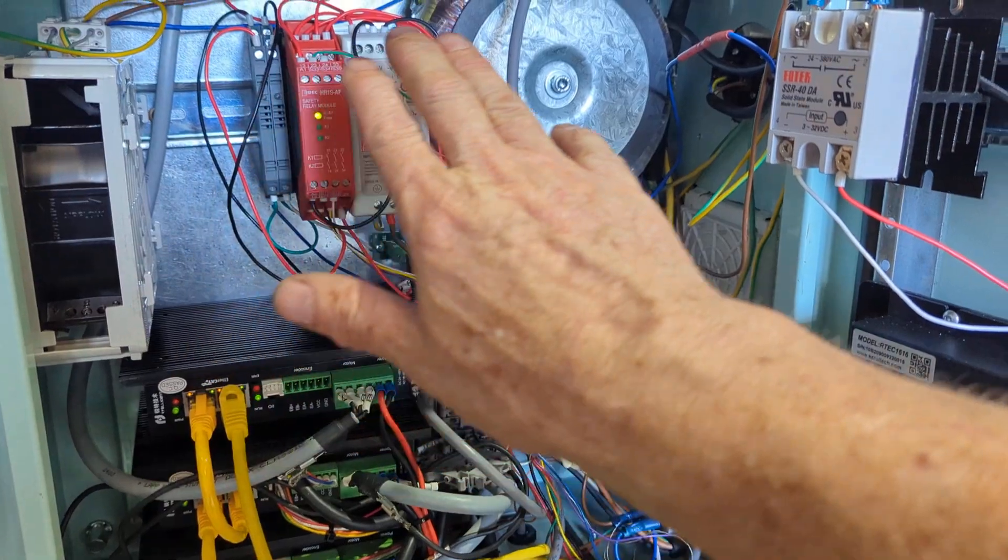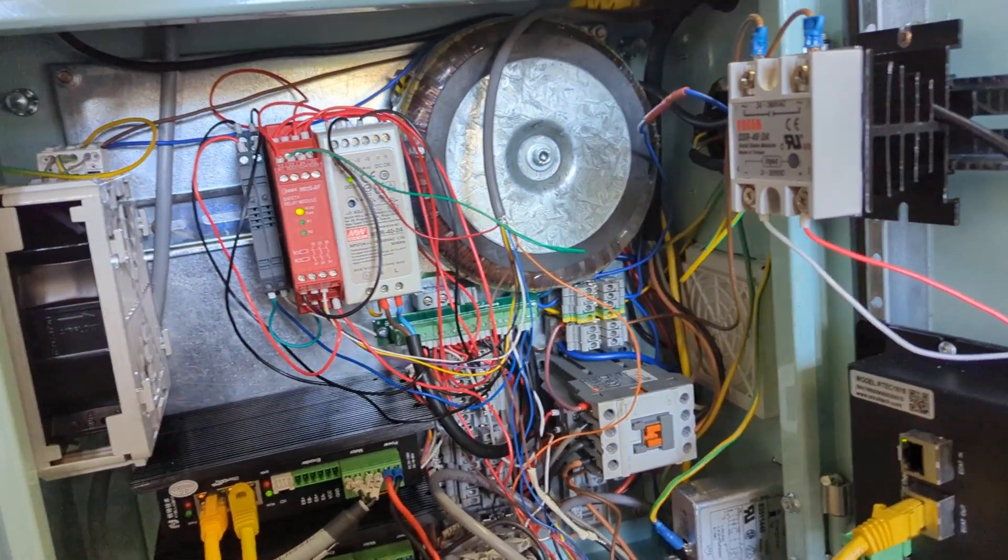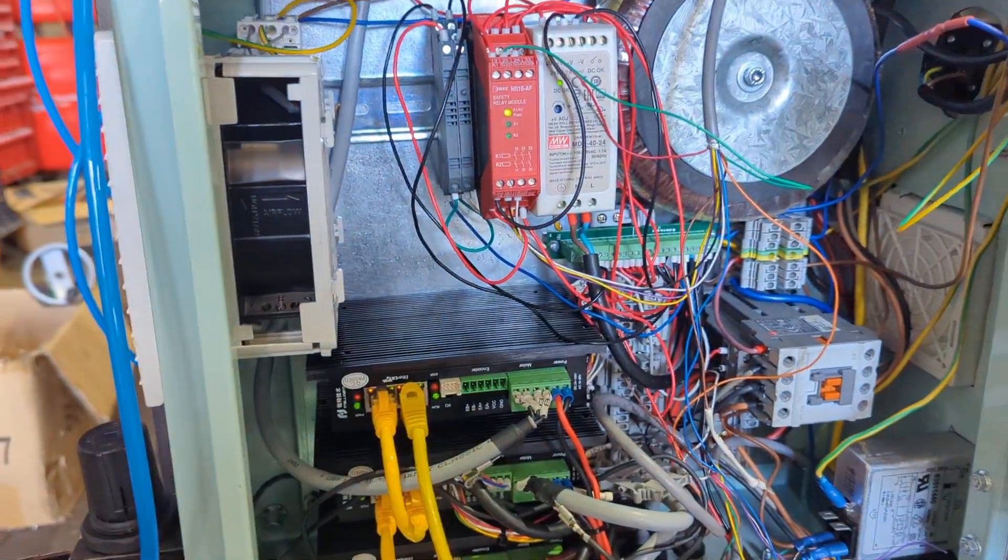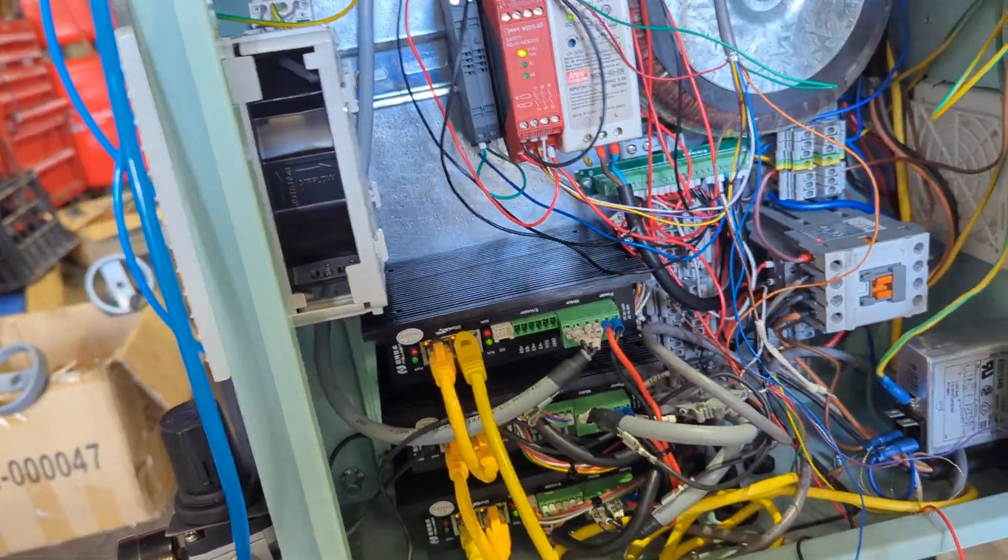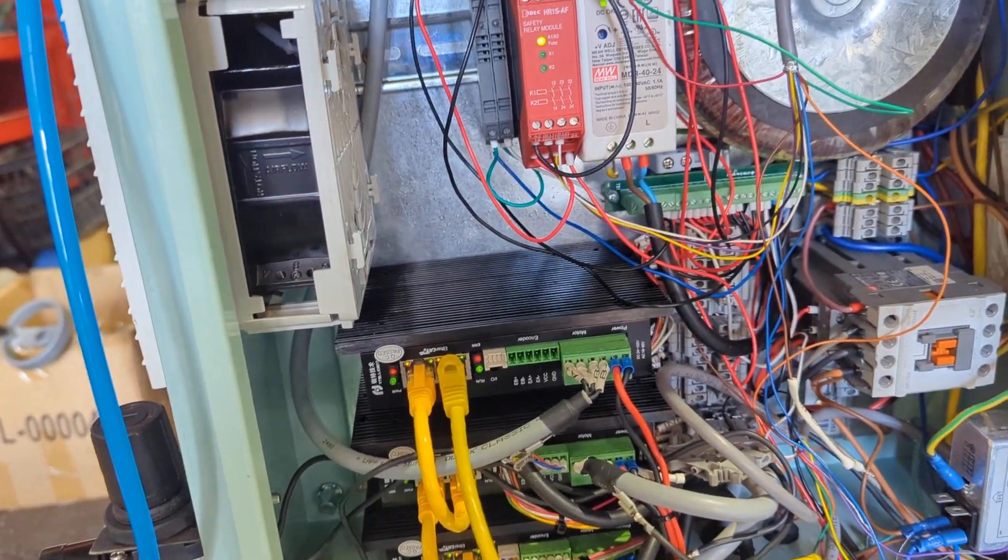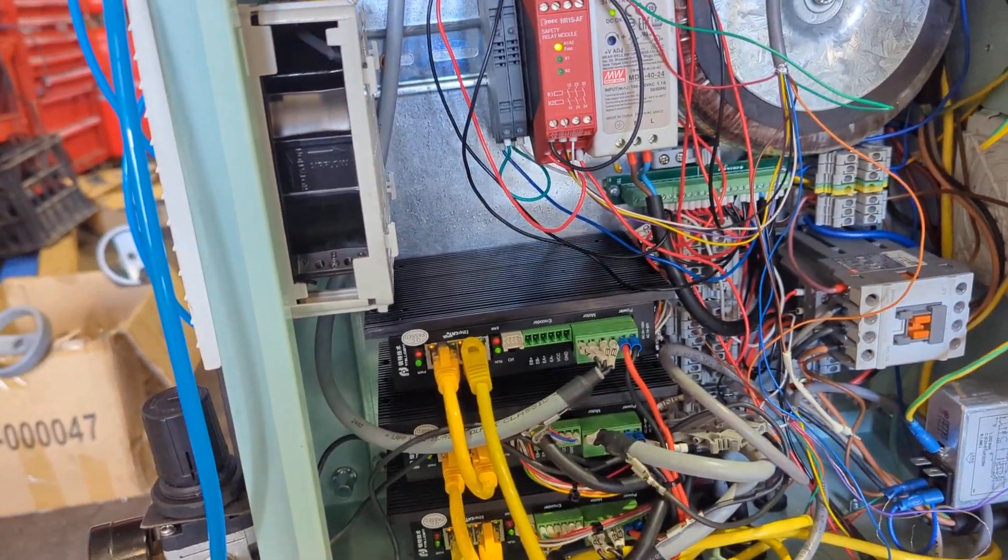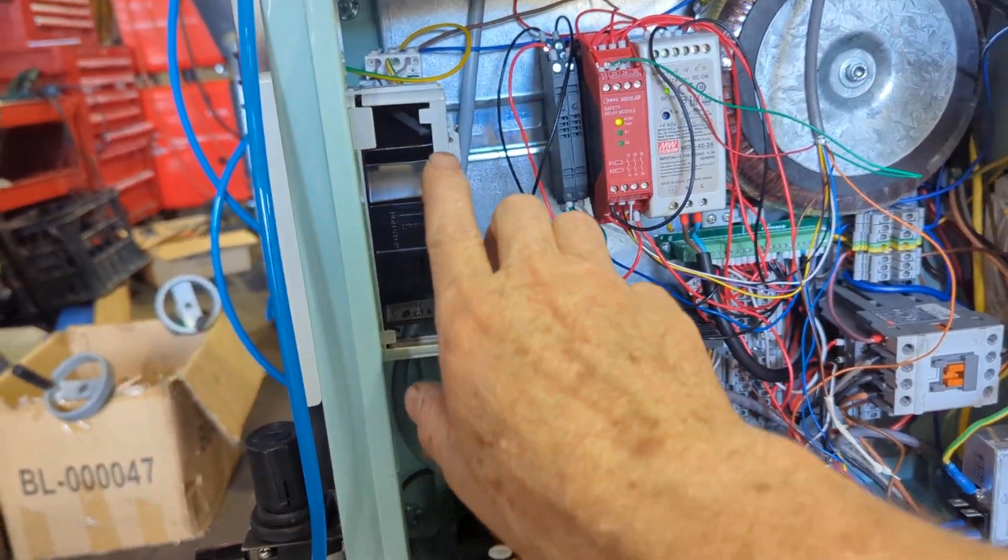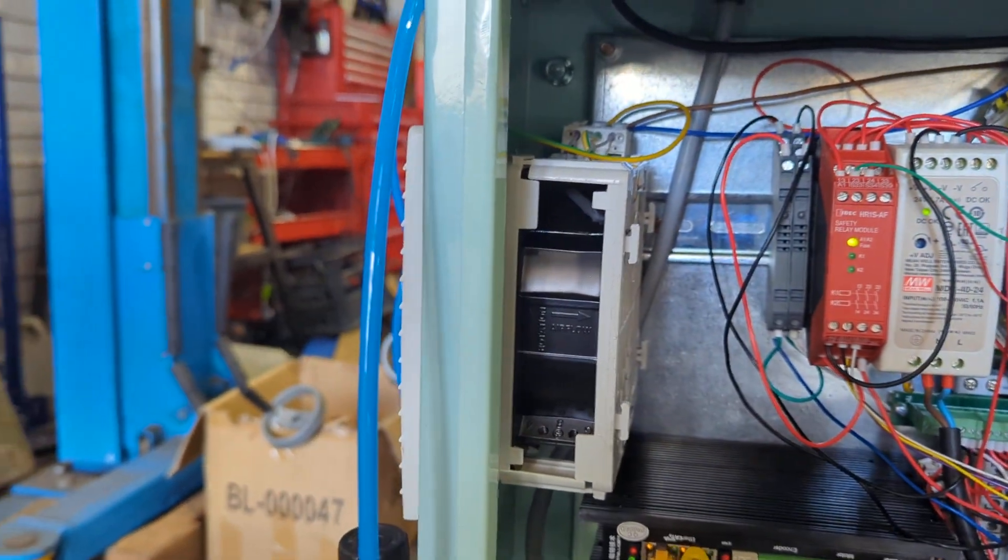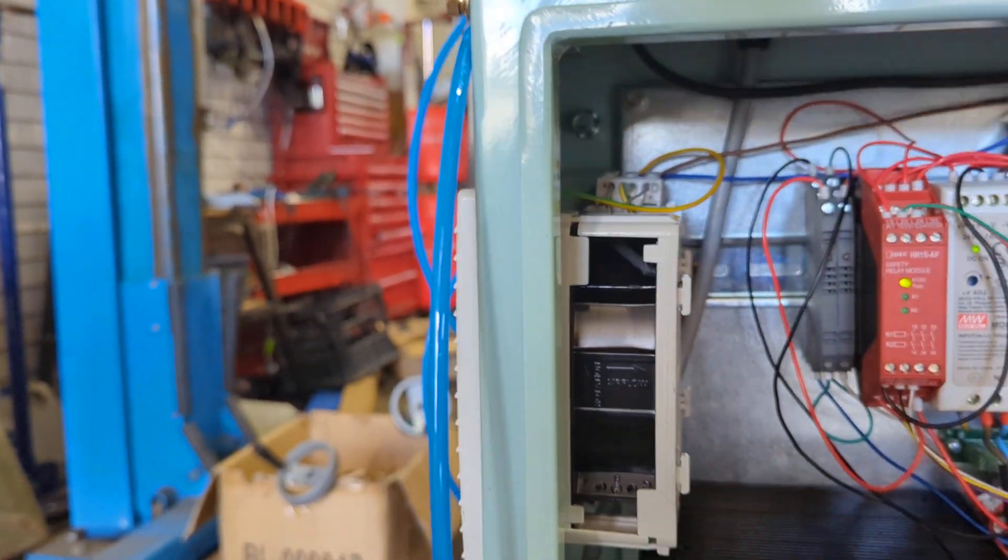I assumed that being a square enclosure the backing board was square, but it's not, and I laid it out on the assumption that this would be the top so the drives were up high and allowed to radiate heat and allow air flow to go through here. But when I took this board from home and came back here, once the cabinet was on the machine, I found that it wasn't square and I had to lay it out this side and I wasn't going to rearrange it. So at that point I decided to put a decent fan in here, so it's got an industrial quality 240 volt fan and I've got that triggered by e-stop.